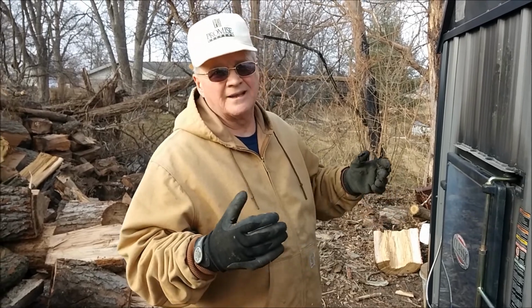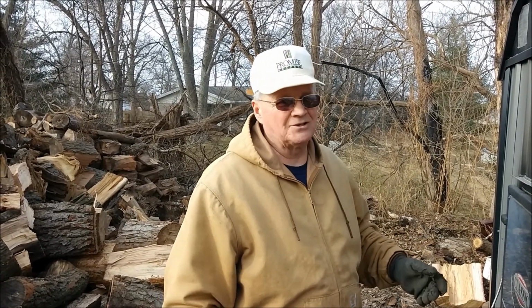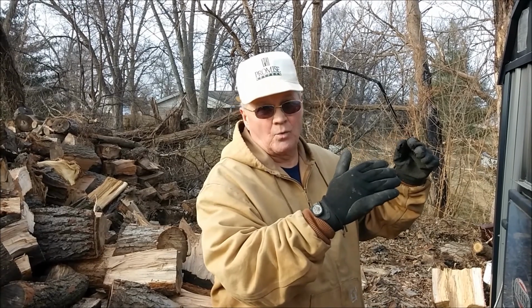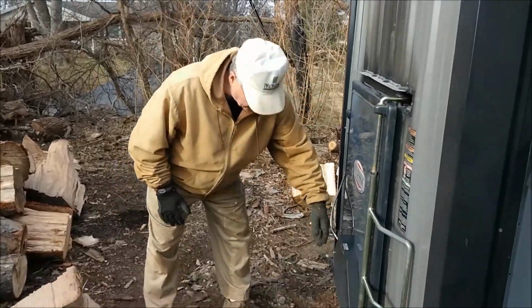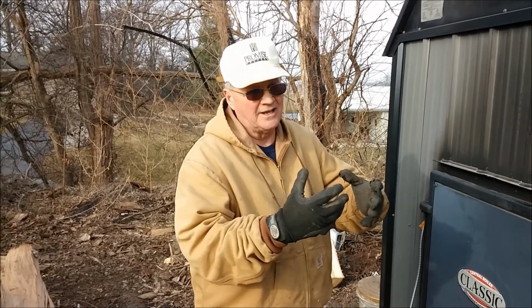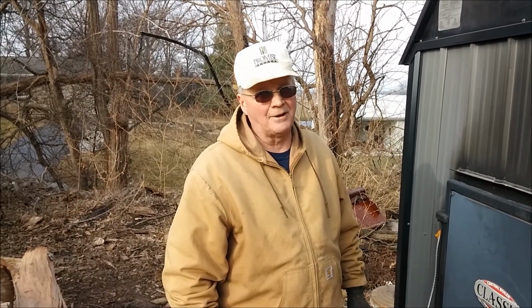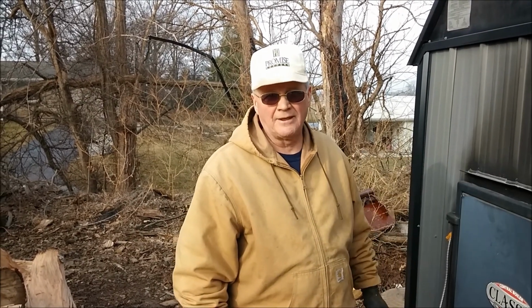Everything that happens here happens slowly. When we first bought it, I would come out and build a fire, and I would come back the next morning, and the wood would all be black and look like charcoal, no fire, no smoke out the chimney or anything, and I thought it was going out. But the truth of it turned out to be that when the water gets the temperature that it wants inside, then there's like a guillotine right down here that goes over the few little holes that allow air inside, and it actually just nearly suffocates the fire, but not completely. There's just enough to keep it going. That's the mode that we're probably in now.